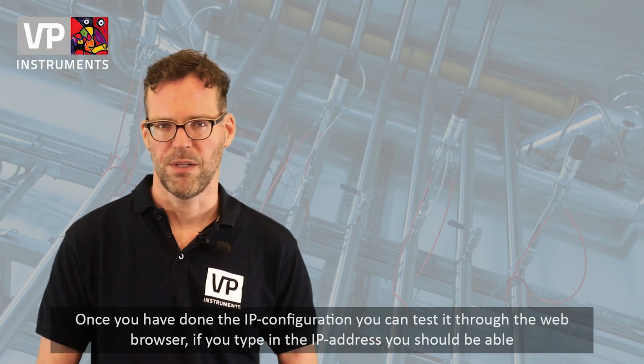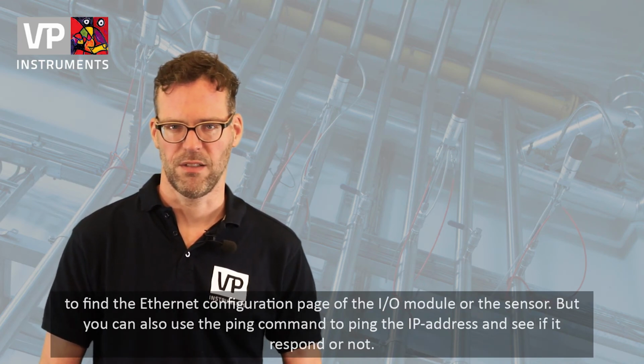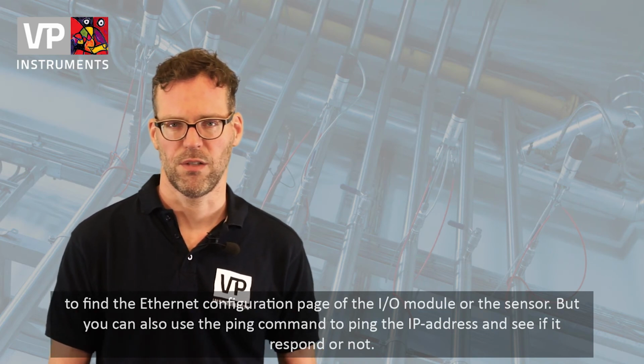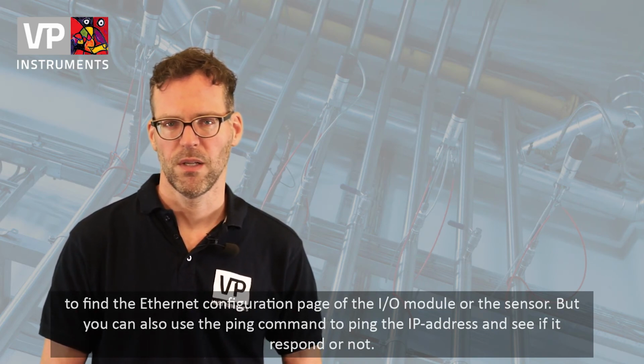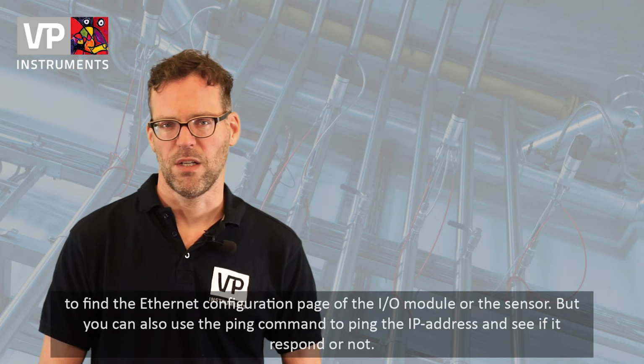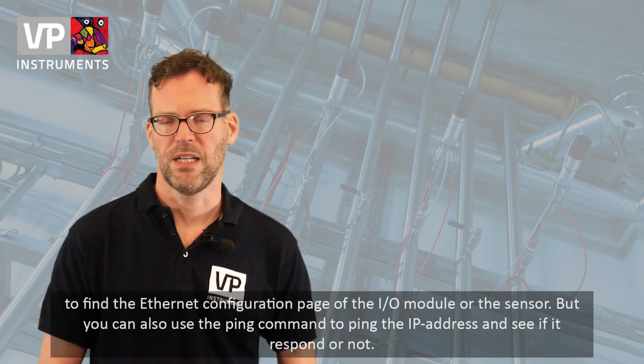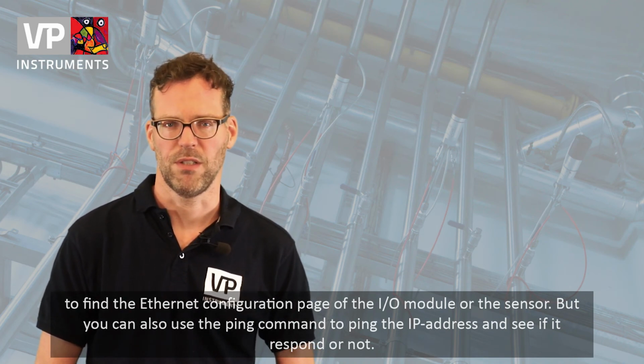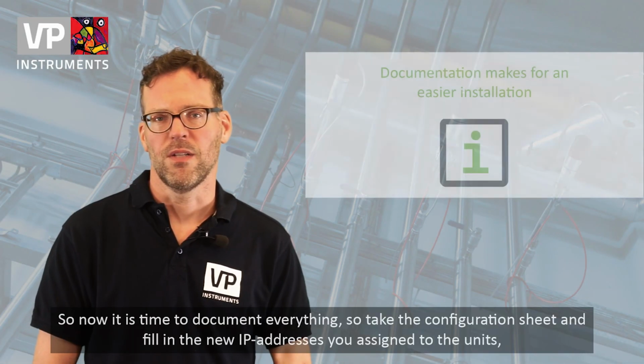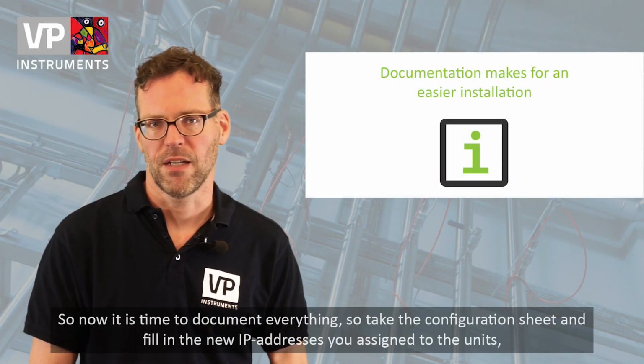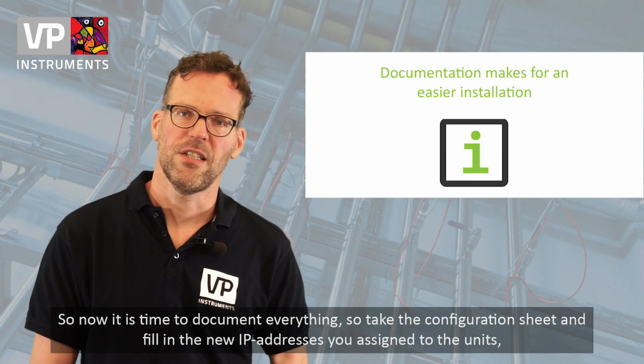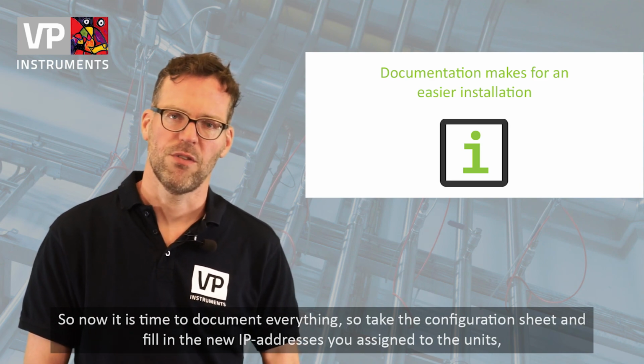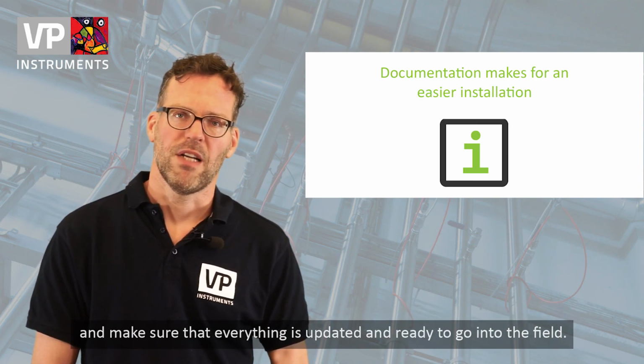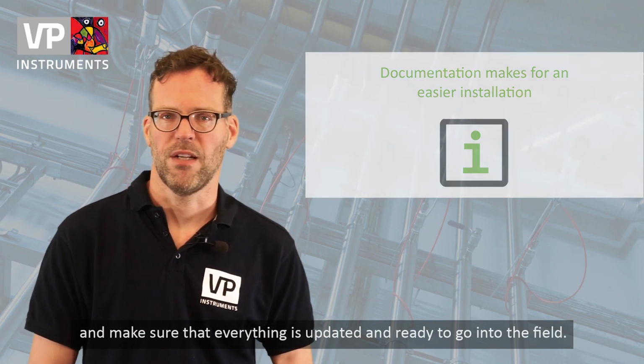If you type in the IP address, you should be able to find the Ethernet configuration page of the I/O module or the sensor, but you can also use the ping command to ping the IP address and see if it's responding properly. So now it's time to document everything. So take the configuration sheet and fill in the new IP addresses you assign to the units and make sure that everything is updated and ready to go into the field.